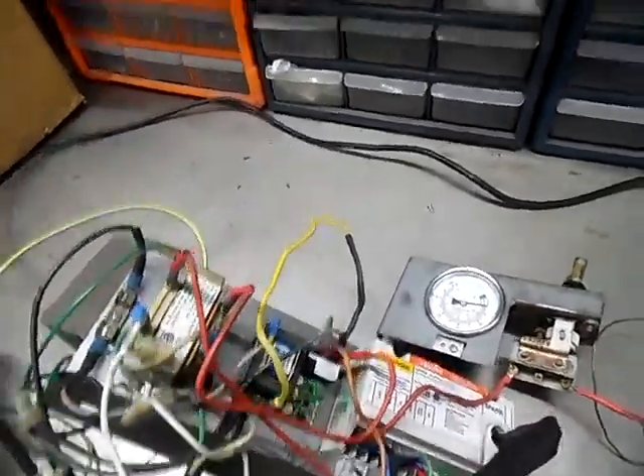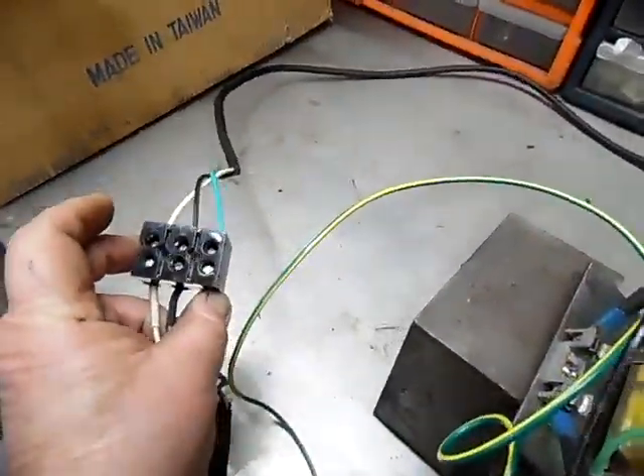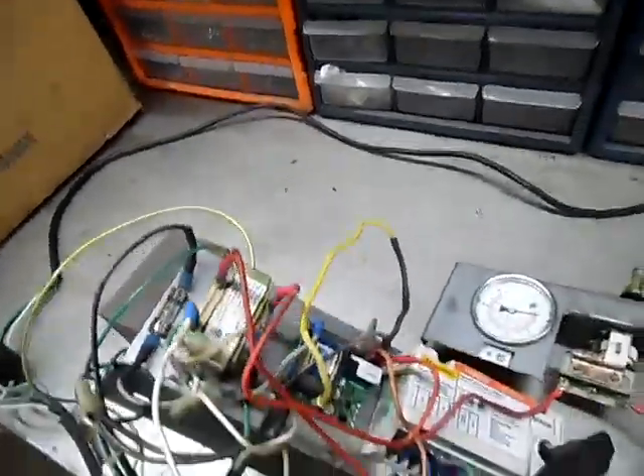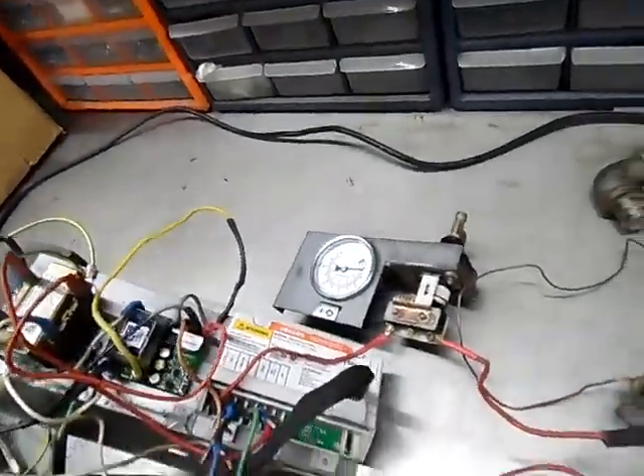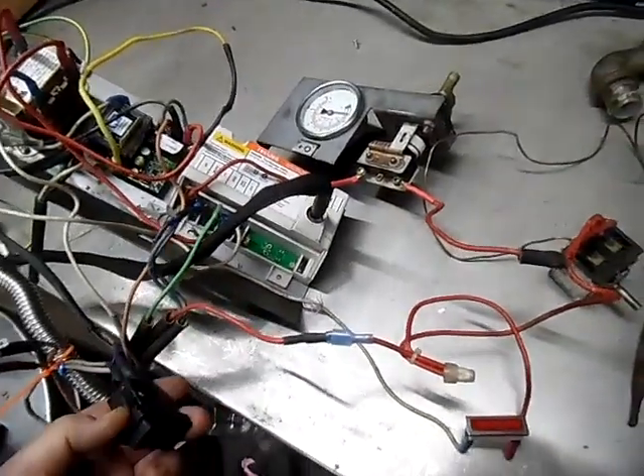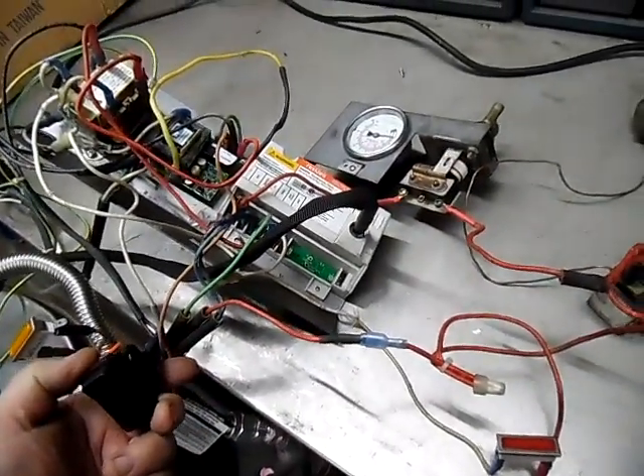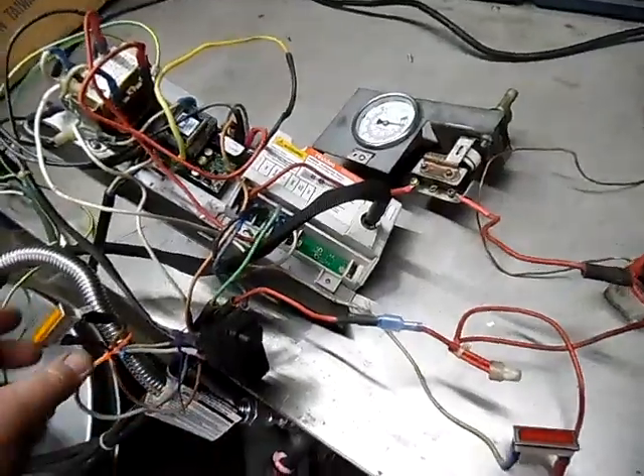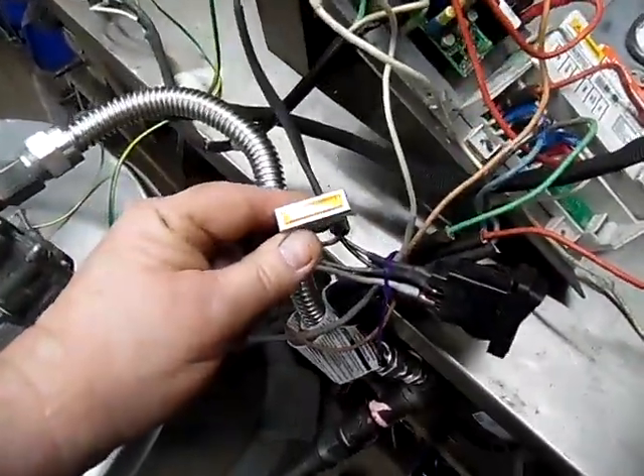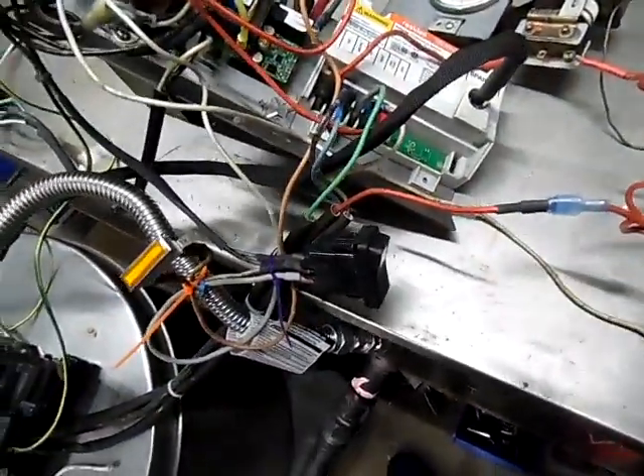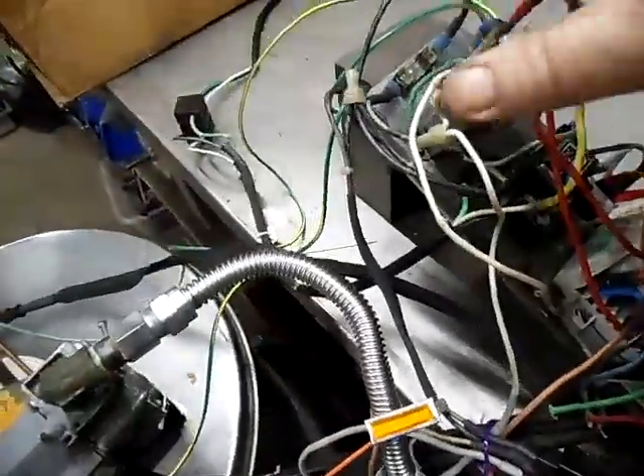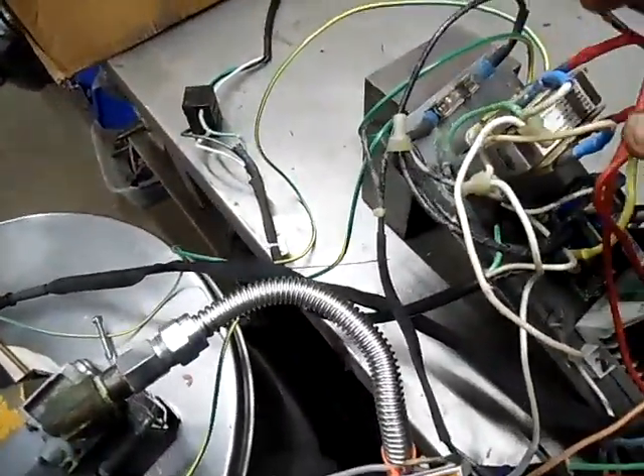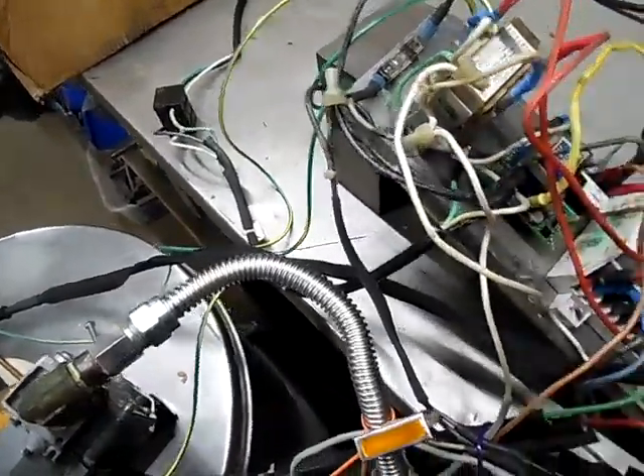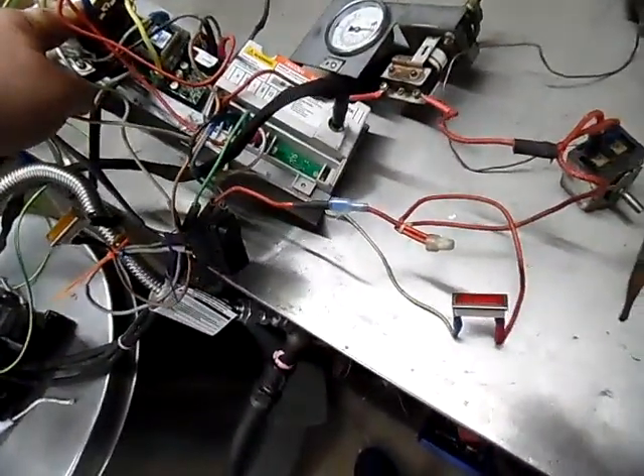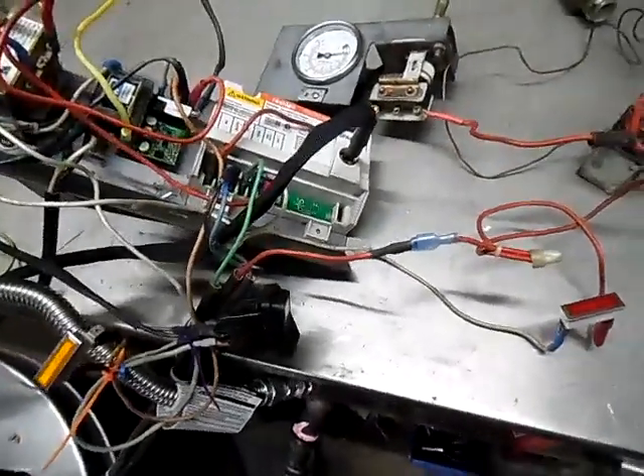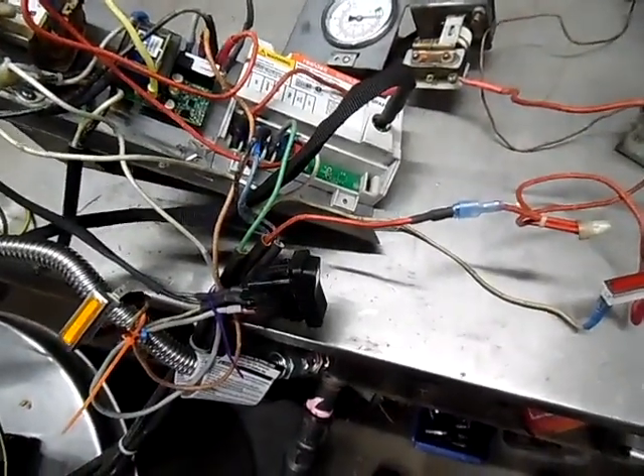nothing turns on. You've got your main power cord that comes into a terminal block. It's 115 volt. It runs into your switch. One side of the switch will send power to the transformer. The other side will send it to your water light, which is an amber light. So if you don't have power, the first thing you're going to do is meter across your fuse and make sure your transformer is coming on. If you have 115 to the machine, but you don't get 24 volts out of your transformer, then you're going to be looking at this fuse.